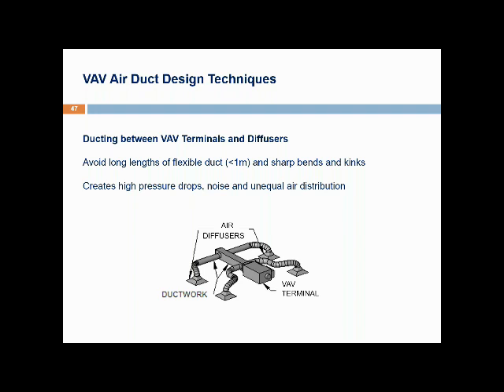For the ducting between VAV terminals and the diffusers, it is very common to use flexible air ducting, but flexible ducting has a high pressure drop. It is important to limit flexible ducting length to a maximum of two meters and to use metal ducting wherever possible. It is also important to avoid sharp bends and kinks in flexible ducting, which create large pressure drops. Sometimes on site installers leave more flexible ducting than needed in the ceiling, creating sharp bends and big pressure drops. Reducing pressure drop downstream minimizes noise and unequal air distribution to the diffusers.